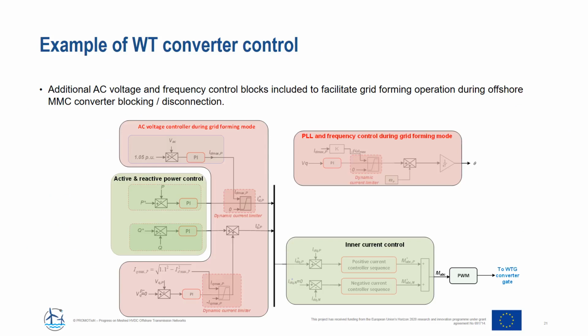The green blocks refer to normal operation, which contains the outer active and reactive power control and the inner current control. In order to maintain the offshore network when the control from the HVDC converter is lost, additional control functionalities are added as shown in the red blocks, so the wind turbines are switched to grid forming mode to control their own AC voltage and frequency in order to facilitate rapid system restoration after fault isolation.